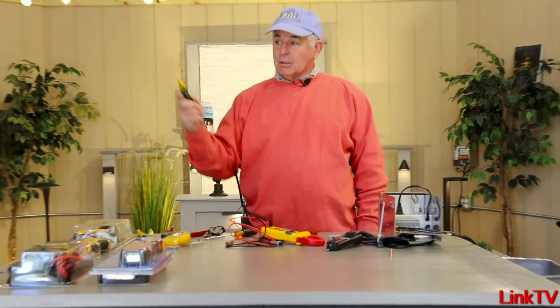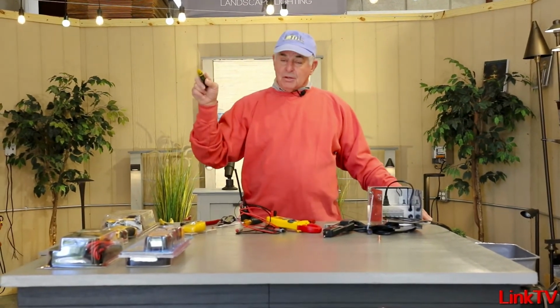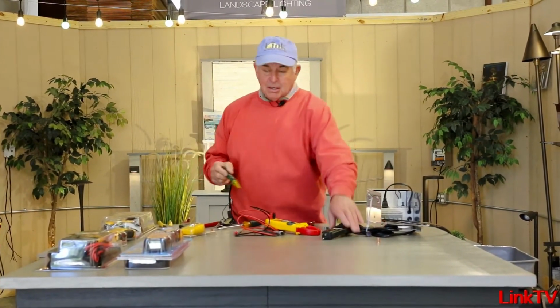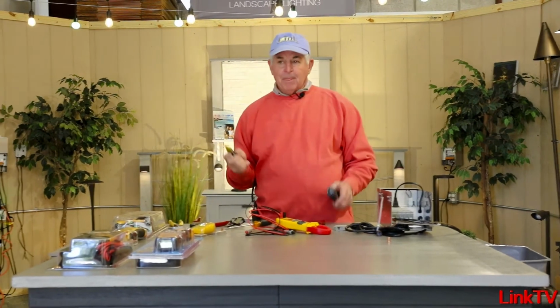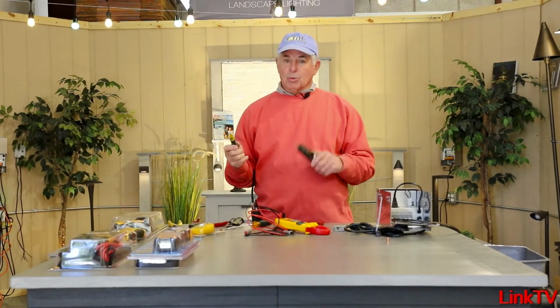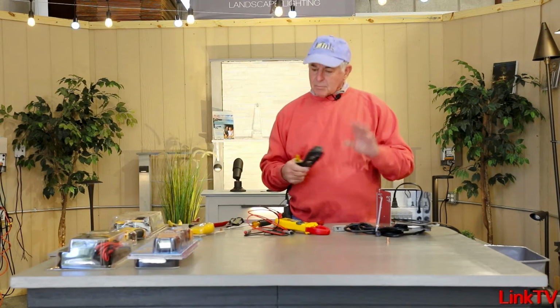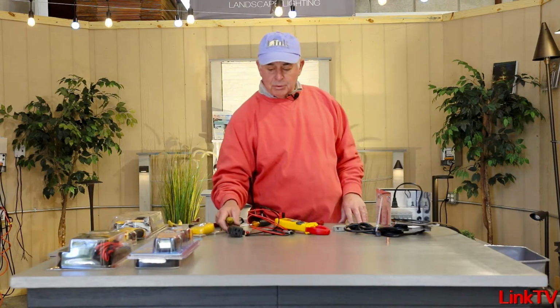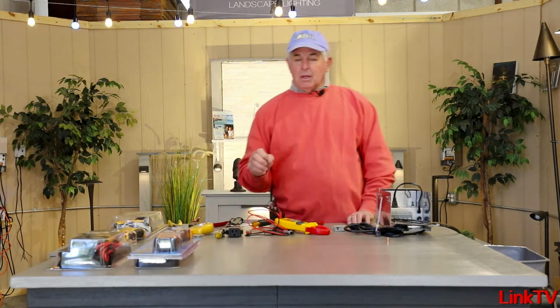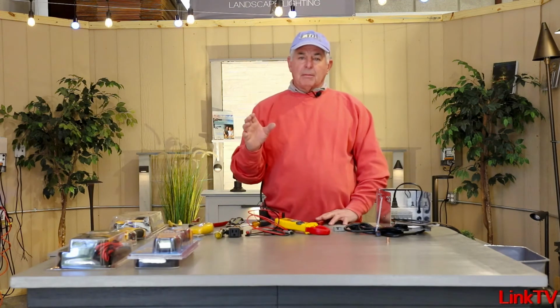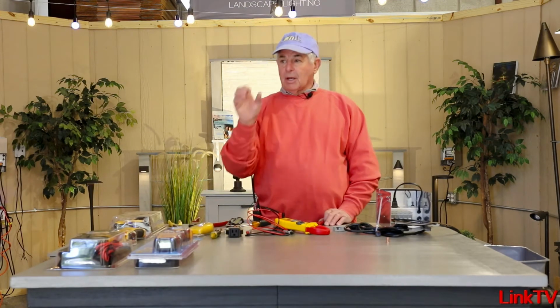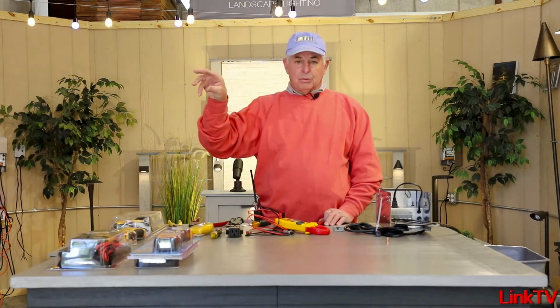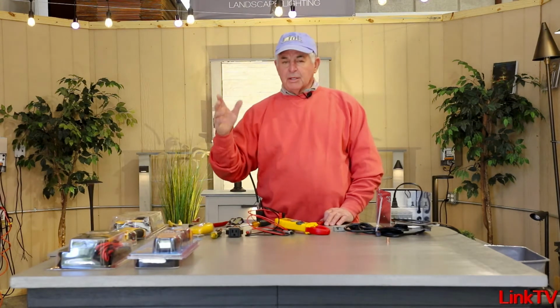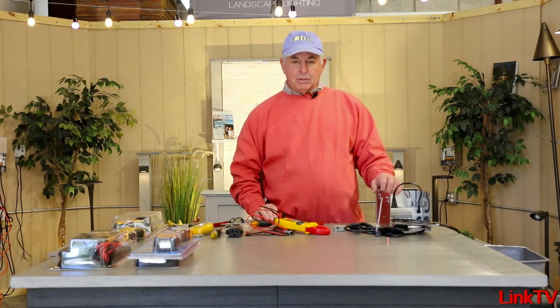We're finding a good live receptacle to pull power from. If you get to a receptacle that doesn't light up or beep, ask if it's a switched receptacle. If it is, we have timers. Intermatic makes an astronomical timer that goes right in the box where the switch was and controls the lights automatically. It's a pretty slick setup.